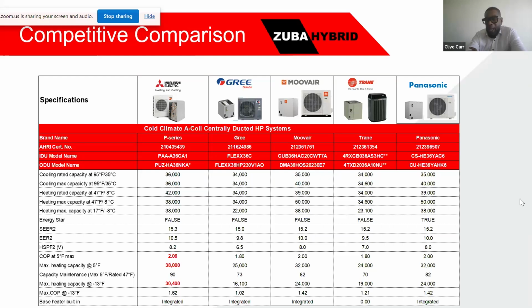So the heating output at low ambient temperatures is key in the performance of a cold climate air source heat pump. And you can see that typically a cold climate air source heat pump is expected to maintain 100% of its rating down to temperatures as low as -15, and you could have operating extension down to -35. Typically, once you get below -30, the efficiency of the air source heat pump may be equivalent to that of electric resistance, where it's at 100%. And you may need to switch to an auxiliary heating source for the colder temperatures throughout the winter.